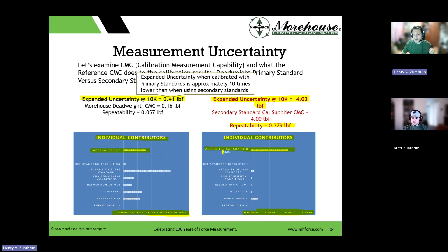when I'm on the left-hand side, what do I focus on? What's the largest thing? The stability. That's the frequency of calibration. If I have a 2-year interval and I'm not happy with that 0.41 pound uncertainty, maybe I need to shorten it. Most people would love a 0.41 on 10,000. So whatever the interval is on this, you'd probably be happy with it. But if you did want to improve the system, that graph tells you immediately that stability is the thing to tackle.